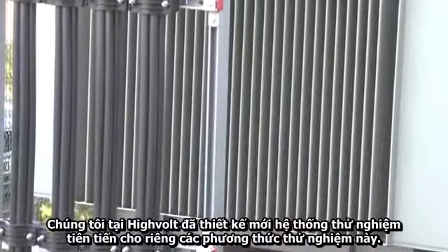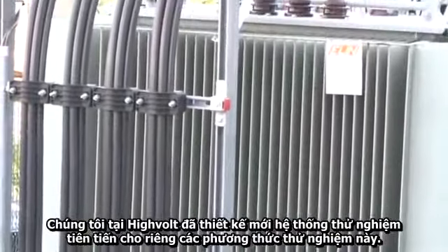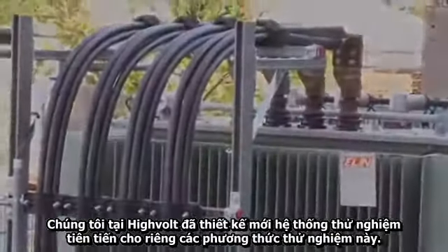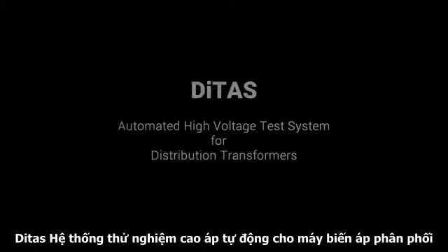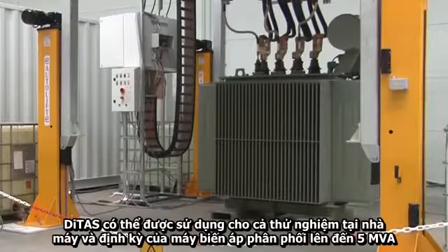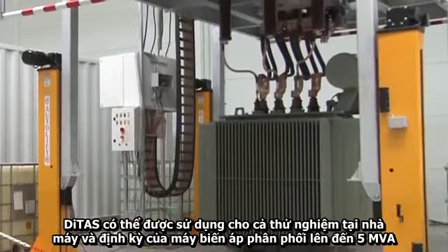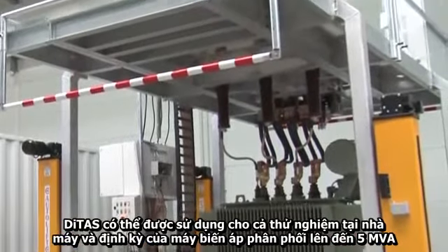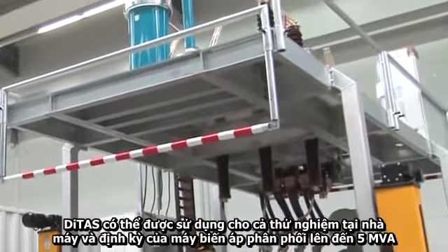We at Highvolt have newly designed a state-of-the-art test system for precisely these tests. DiTAS, Automated High Voltage Test System for Distribution Transformers. DiTAS can be used for both routine and type testing of distribution transformers up to 5 megavolt ampere.